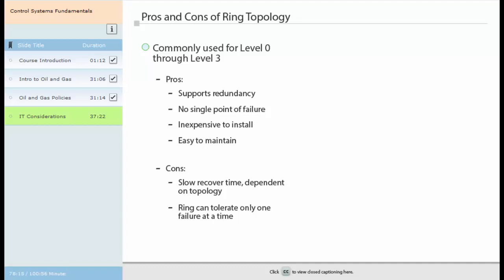In the ring topology, Ethernet network loops are managed by means of spanning tree or rapid spanning tree protocol, which require anywhere from 6 to 50 seconds to recover from a network failure, depending on whether STP or RSTP is used. When a resilient Ethernet protocol is implemented, network and application convergence typically occurs within 200 milliseconds and can be as fast as 50 milliseconds when the protocol is configured over fiber optic uplinks.